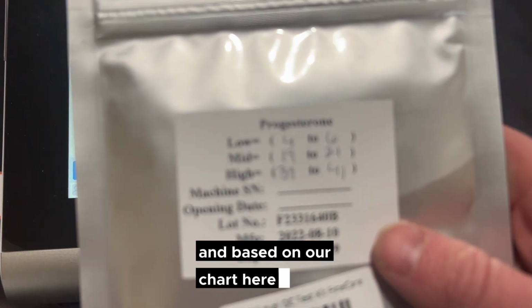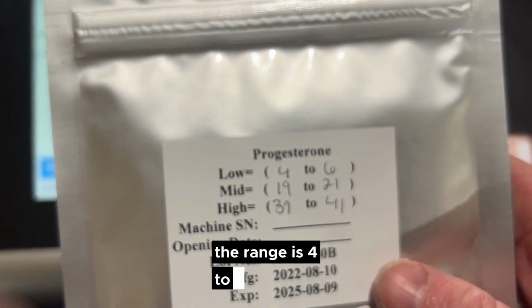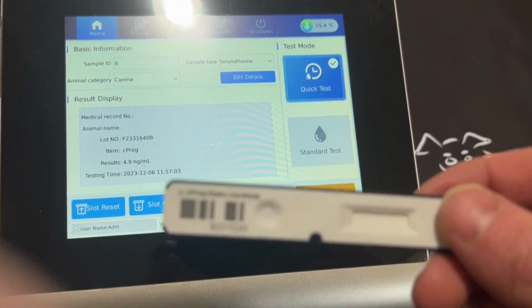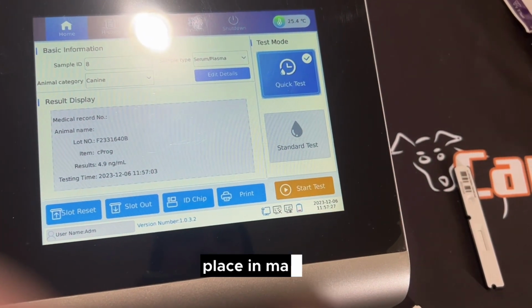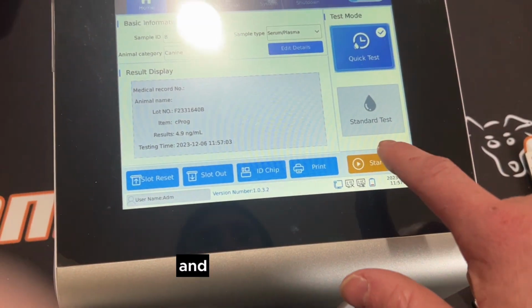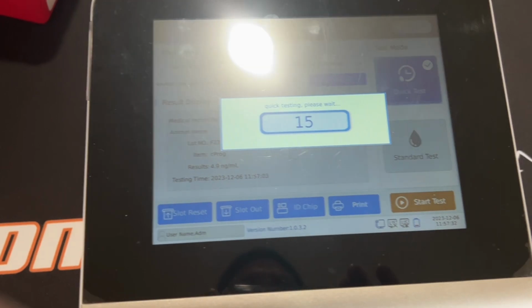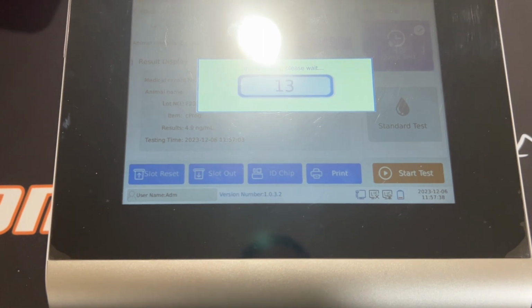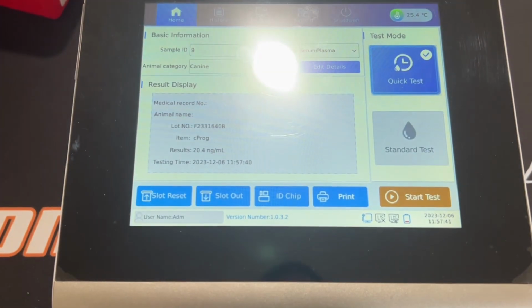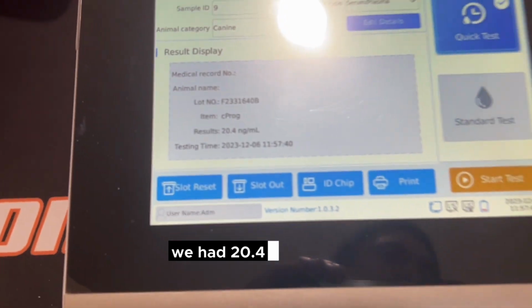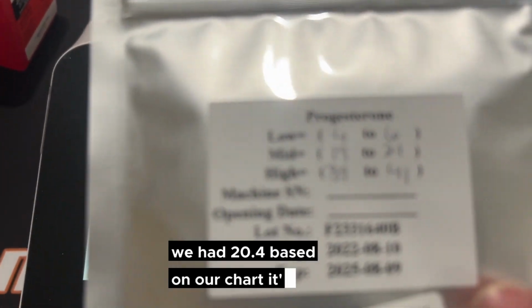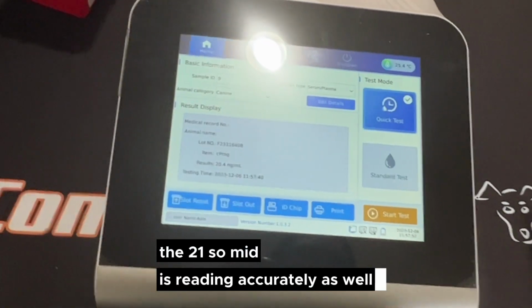Looks like we had a 4.9, and based on our chart here for low, the range is 4 to 6, so the low end is working accurately. Next we'll do the mid. We're going to do exactly the same thing. Place it in the machine and run on quick mode. We got 20.4. Based on our chart, it's 19 to 21, so mid is reading accurately as well.